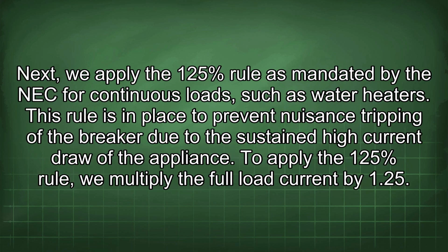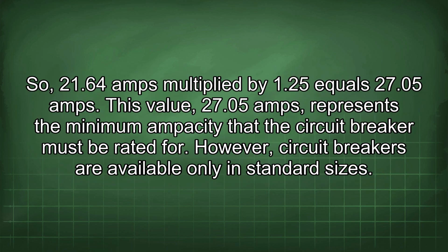Next, we apply the 125% rule as mandated by the NEC for continuous loads, such as water heaters. This rule is in place to prevent nuisance tripping of the breaker due to the sustained high current draw of the appliance. To apply the 125% rule, we multiply the full load current by 1.25. So 21.64 amps multiplied by 1.25 equals 27.05 amps. This value, 27.05 amps, represents the minimum ampacity that the circuit breaker must be rated for.